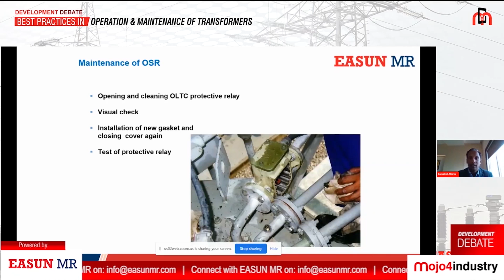the OSR gets operated with the help of the oil flow. You can see here, I think whether it is visible or not, the arrow mark should point to the conservator side and it should be installed in the proper way, and it should be tested whether it is connected to your breaker or not. Sometimes what happens is this OSR is not connected, because the OSR needs to be connected to your circuit breaker, because this is the only protection device you have for the tap changer.